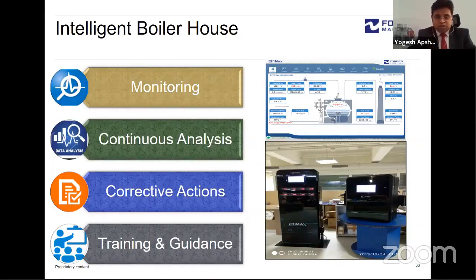What is this intelligent boiler house doing? So we monitor all the parameters on the boiler with hardware equipment. We have a steam flow meter which monitors the steam. We have fuel flow meters. We have O2 analyzers which measure the O2 percentage in the stack. Then we have temperature transmitters which measure the ambient temperature, feed water temperature, stack temperature, and we analyze all this data in a software. So this is the monitoring.